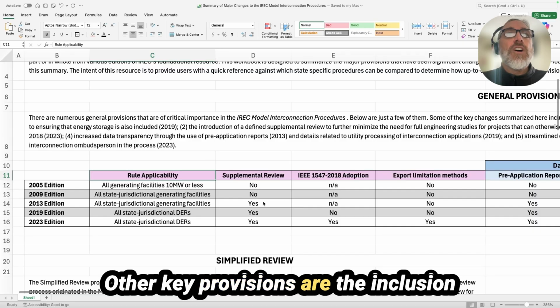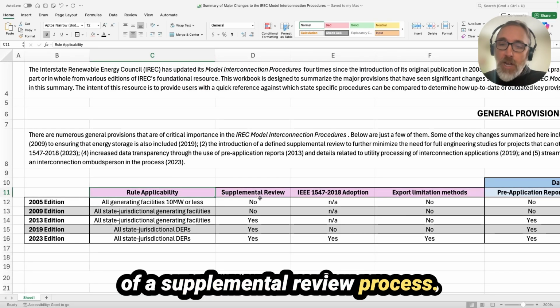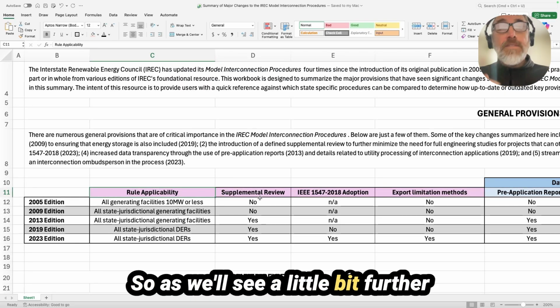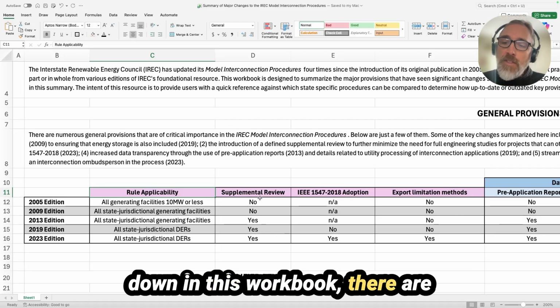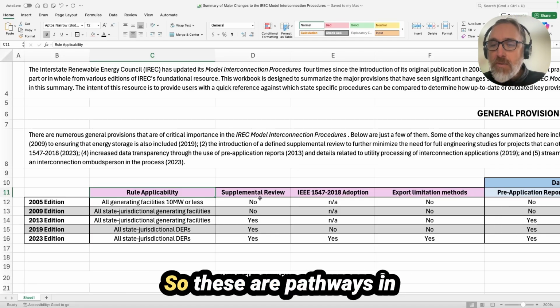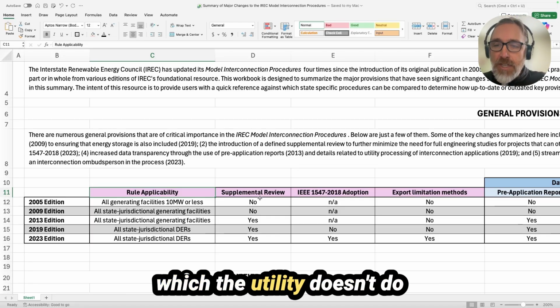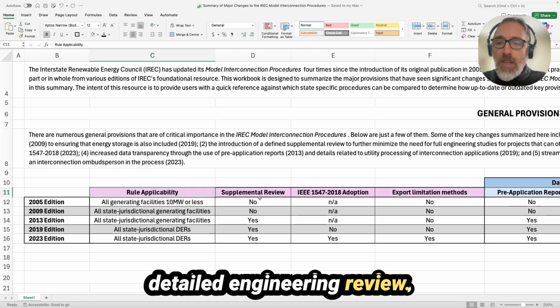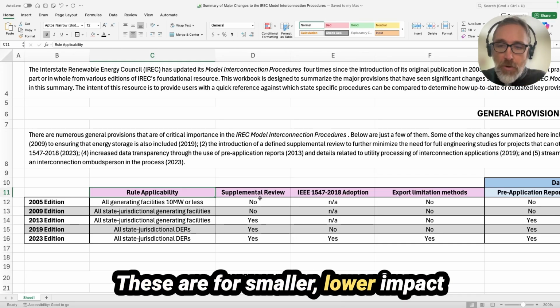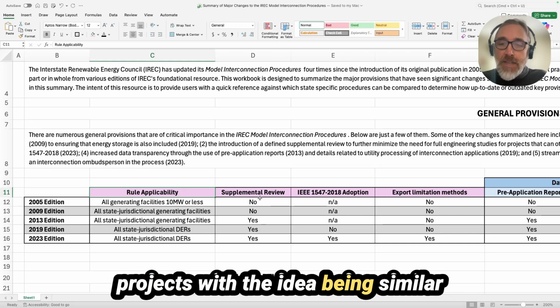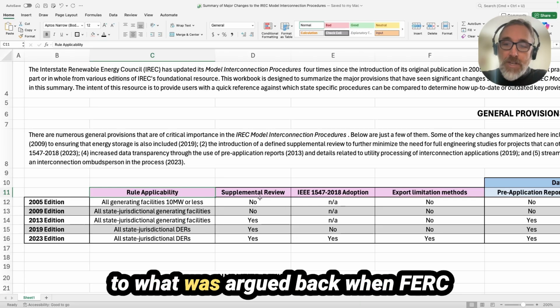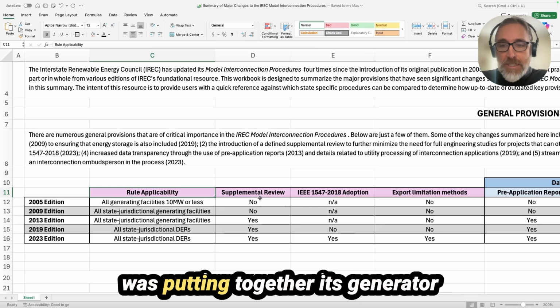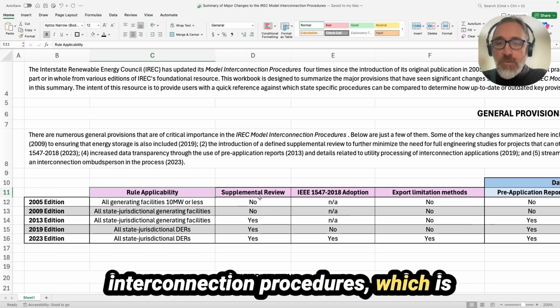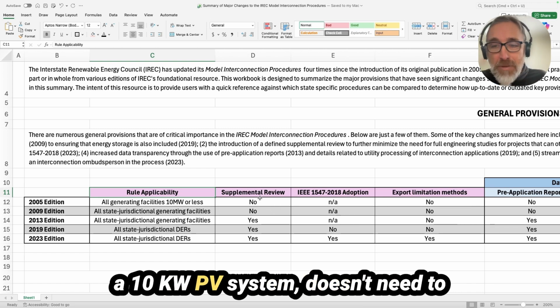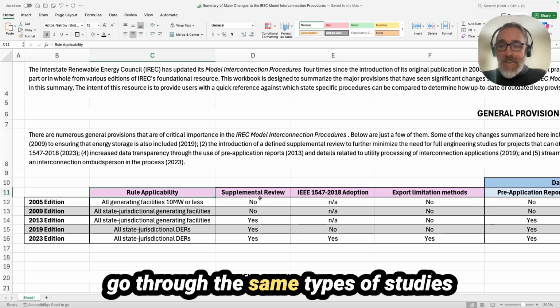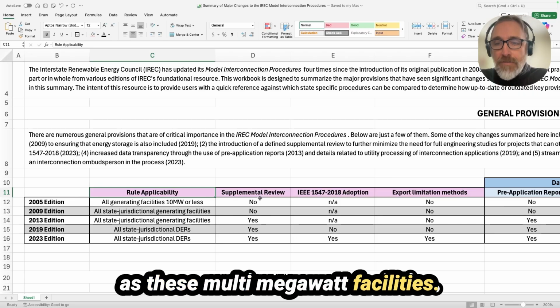Other key provisions are the inclusion of a supplemental review process. So as we'll see a little bit further down in this workbook, there are a couple of screening pathways. So these are pathways in which the utility doesn't do detailed engineering review. These are for smaller, lower impact projects, with the idea being similar to what was argued back when FERC was putting together its generator interconnection procedures, which is a 10 kW PV system doesn't need to go through the same types of studies as these multi-megawatt facilities.